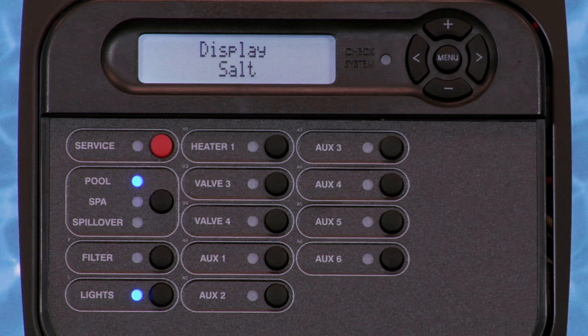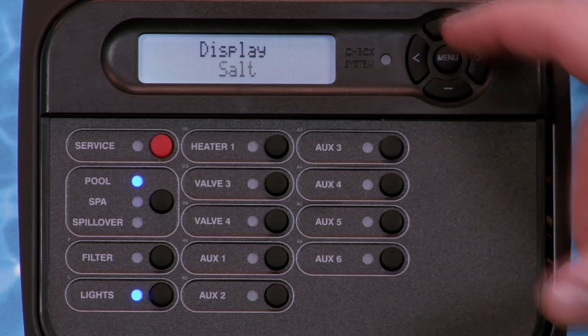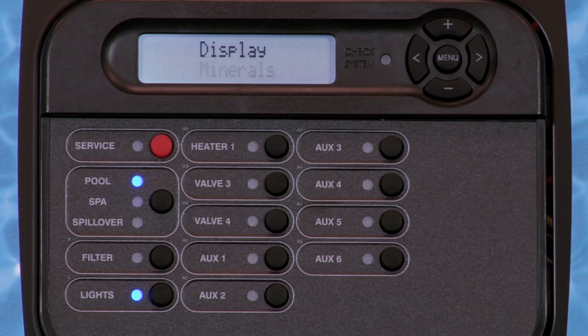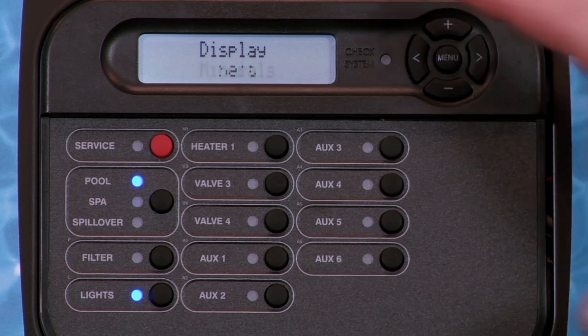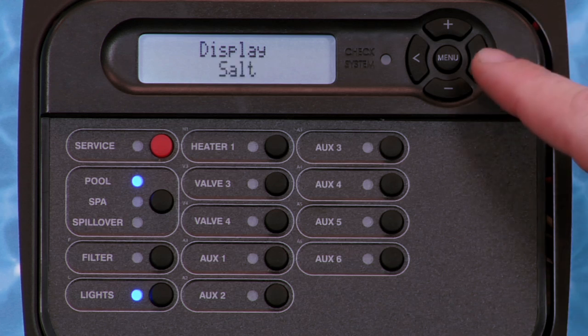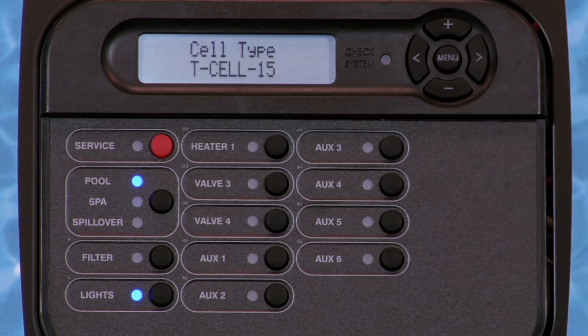Once again, the bottom line is flashing, indicating that this can be changed by pressing the plus key. If the plus key is pressed, the display will change to Display Minerals. Pressing the plus key again changes the display back to Display Salt. Press the right arrow key to move to the next item, which is cell type.